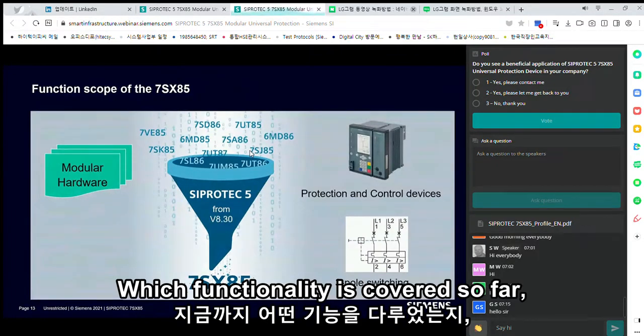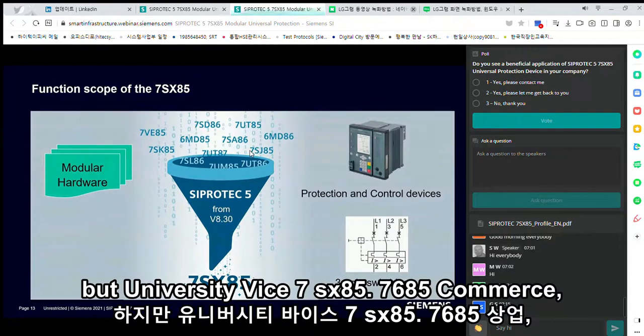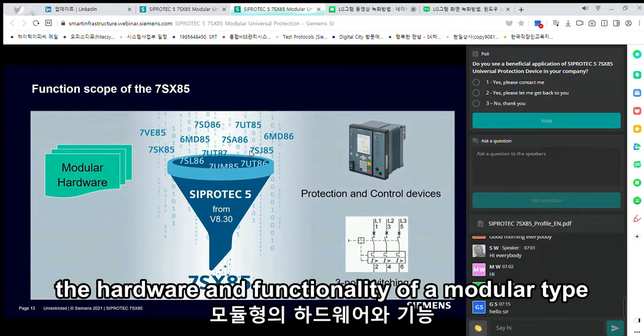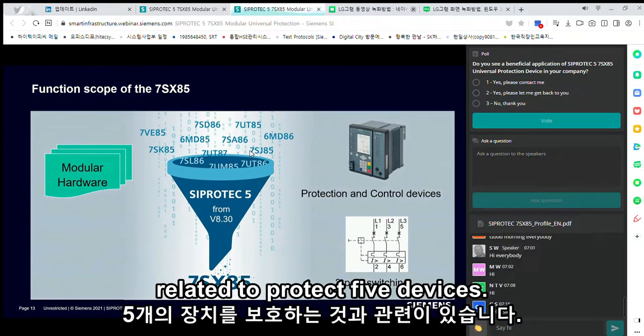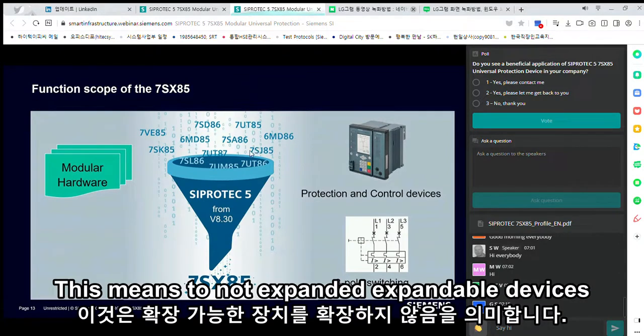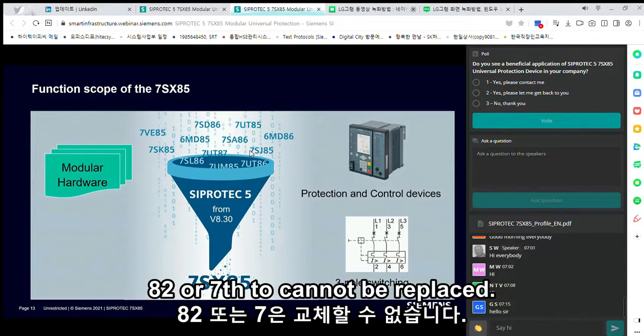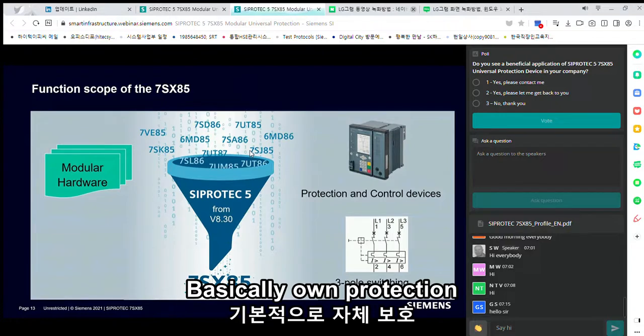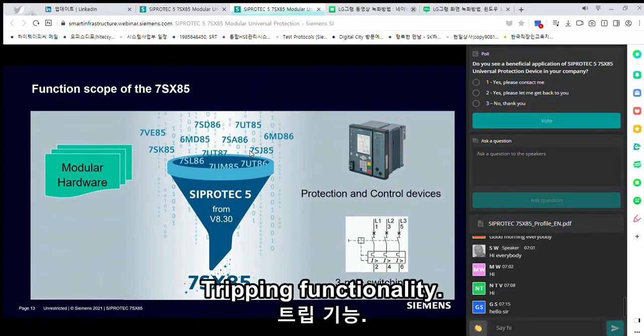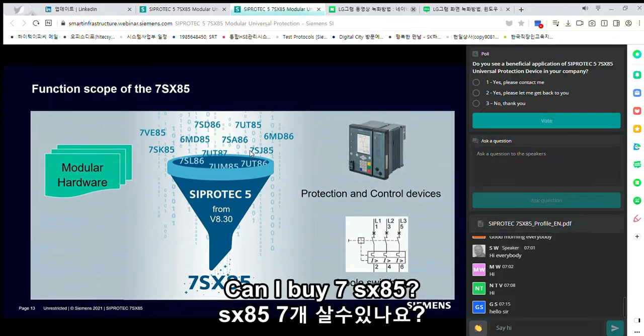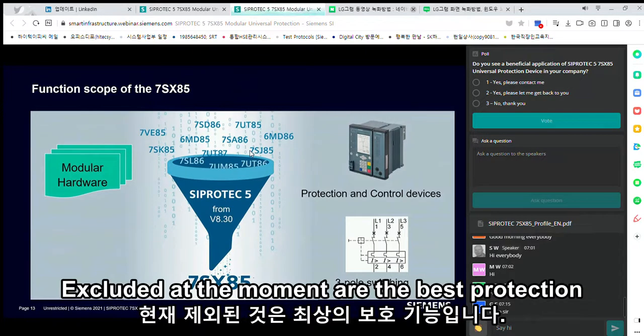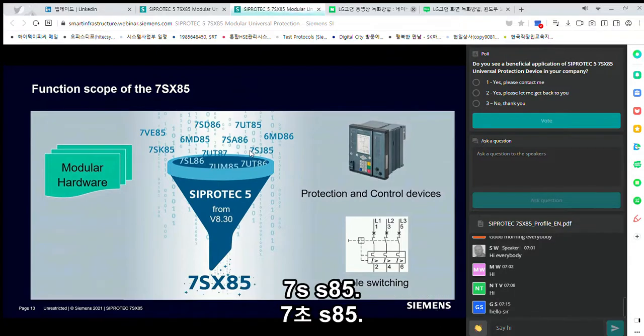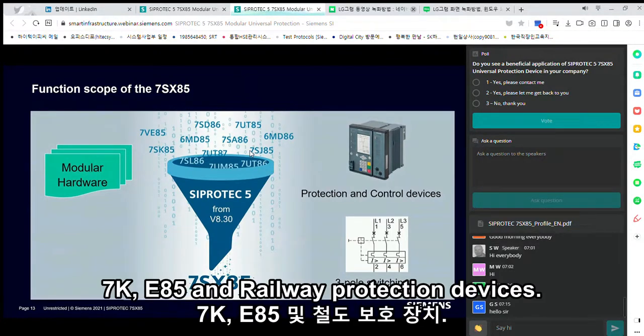Which functionality is covered so far by the universal device 7SX85? The 7SX85 covers the hardware and functionality of our modular type-related SIPROTEC 5 devices. This means the non-expandable devices such as 7SJ82 or 7UT82 cannot be replaced. Basically, all protection and control devices with 3-pole tripping functionality can be covered by a 7SX85. Excluded at the moment are the busbar protection 7SS85, the fault recorder 7KE85, and railway protection devices.